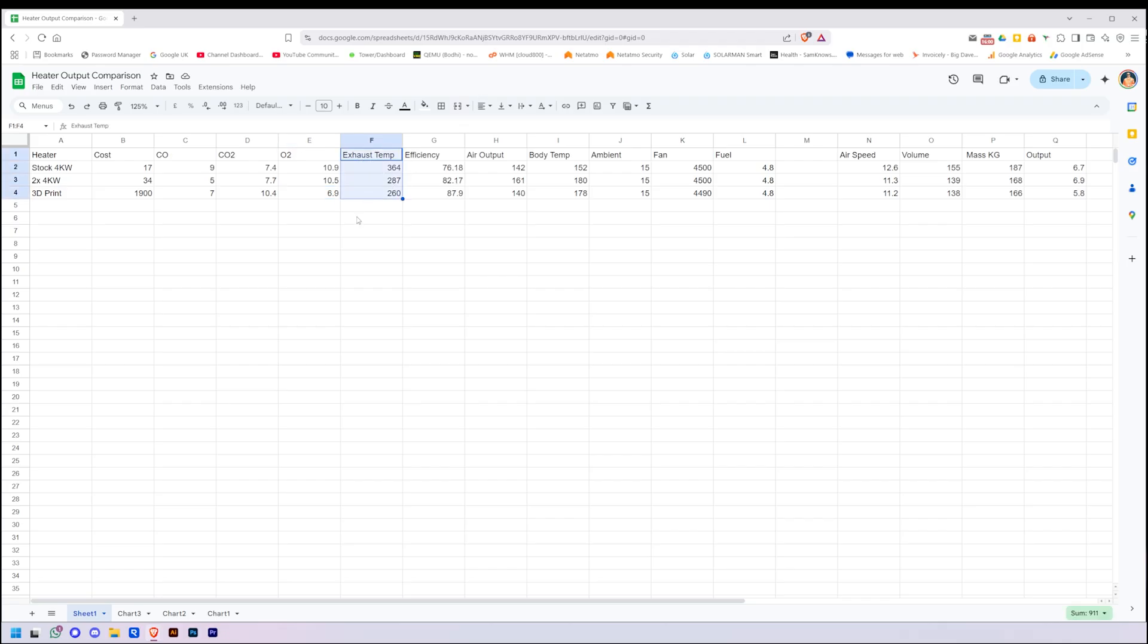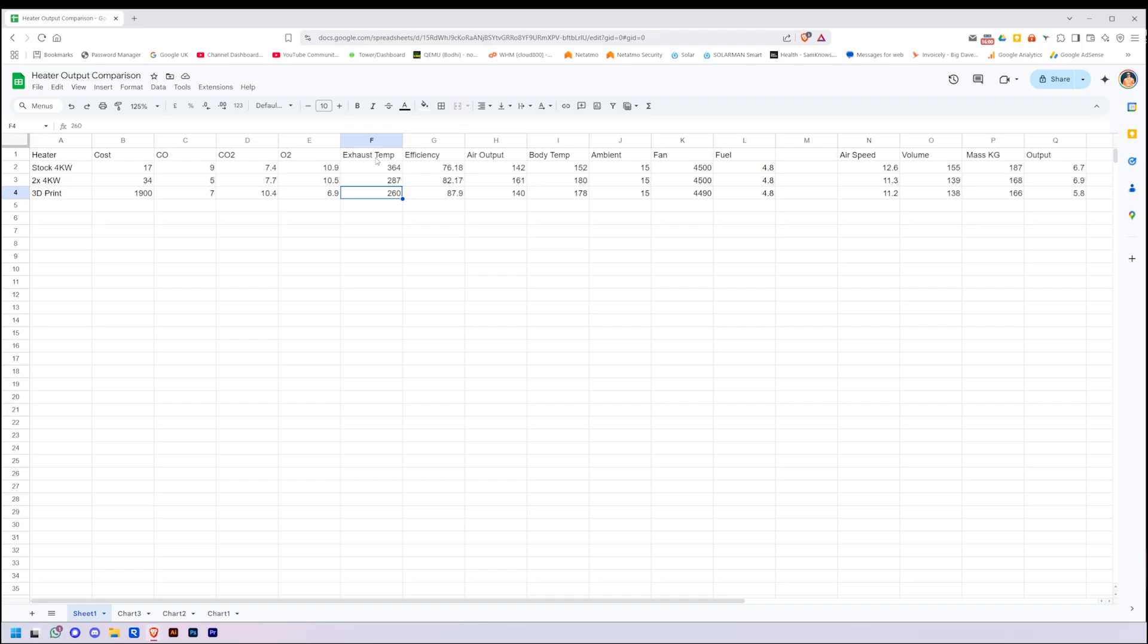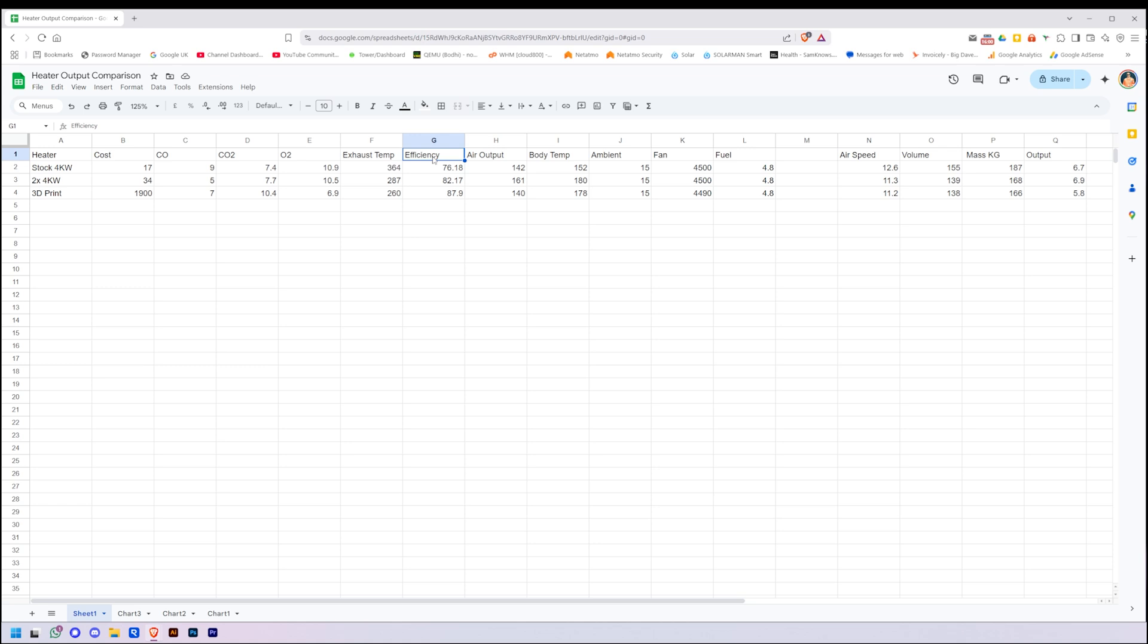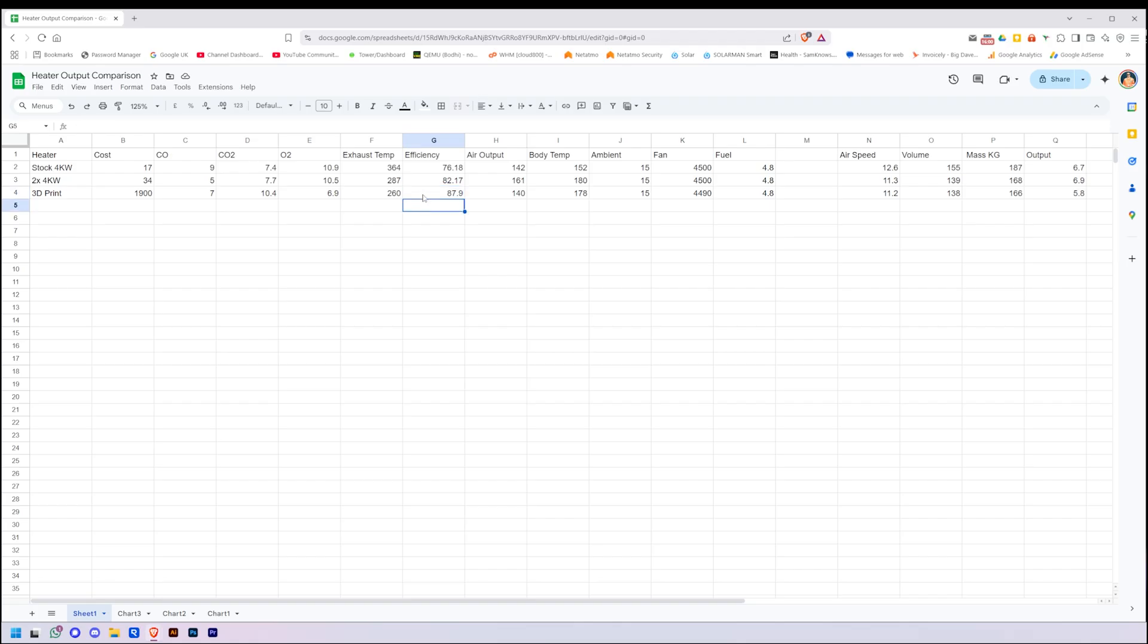Now this bit here is where it's getting interesting. The exhaust temperature. The stock one was 364, two joined together was 287, and the 3D print 260. So what that means is, if the exhaust temperature is cooler, that means the heat is not being wasted out of the exhaust, it's going and heating up the heat exchanger and heating the air. Now the column to the right of that is efficiency, and that is efficiency calculated by the TPI gas analyzer. I don't know what variances it counts for its percentage, but we're taking it as it's the same for all of them. So the change in efficiency must be correct. So we've gone from 76 on stock to 87% on the largest, the 3D printed version.